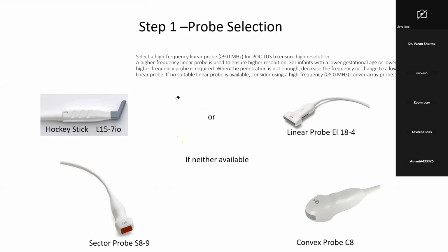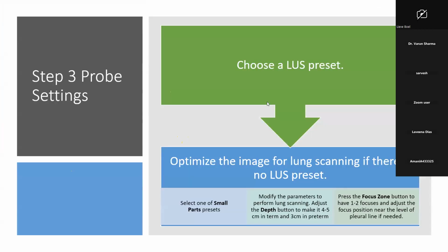Okay, so step one was probe selection. Step two is disinfection. Step three is the preset. Simple. Choose your preset, adjust the depth, and then basically adjust your frequency if you can. If you can't adjust your frequency, you want to optimize the image, and if you're using an old machine, adjust your focus. It's these three parameters that we're going to work with. There is nothing else you need to do.